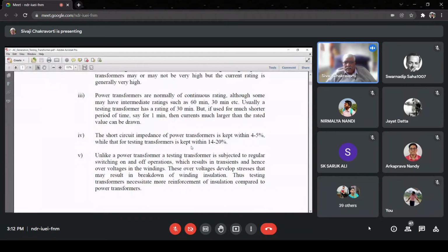Then a very important difference comes, that is what is called the continuous rating. Power transformers, you know that we don't switch off the transformer. When we switch on, it just works 24 into 7 into 365. So they are designed for continuous rating. That means for continuous operation at their rated value. But for a testing transformer, that is not the case. A testing transformer is used only when we test an equipment. And I have already said that testing occurs only for 1 minute. But as you know, to prepare for testing, you require some time, etc. So typically, a testing transformer is rated for 30 minutes, whereas power transformers are continuously rated. So this is another major difference between the two types of transformer.